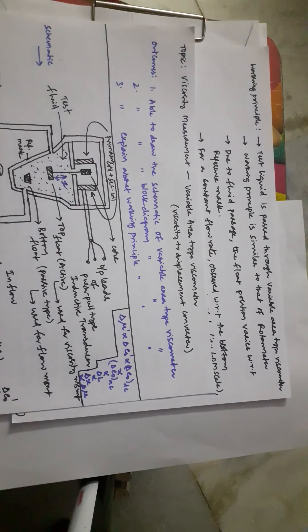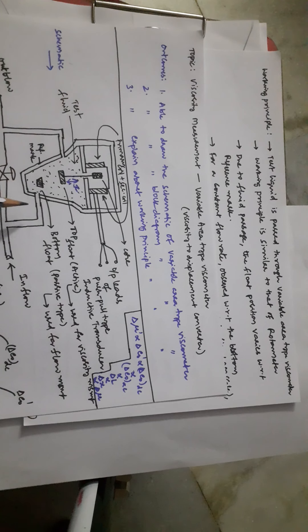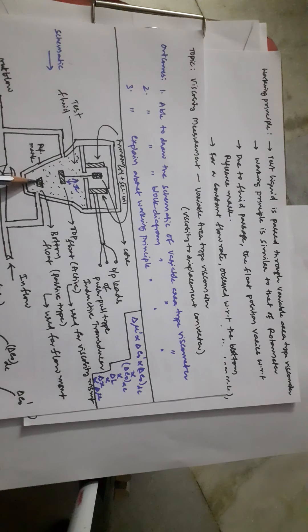Coming to the working principle: the test liquid is passed through the variable area type viscometer, working similarly to a rotameter. Due to fluid passage, the float position varies with respect to a reference mark. The float moves up and takes a sustained position where the upward force equals the downward force, which is the same equilibrium principle as in the rotameter.